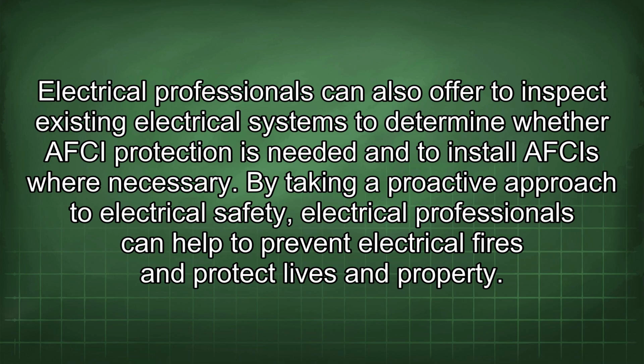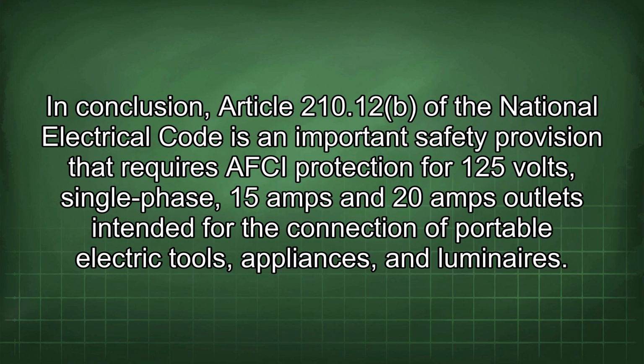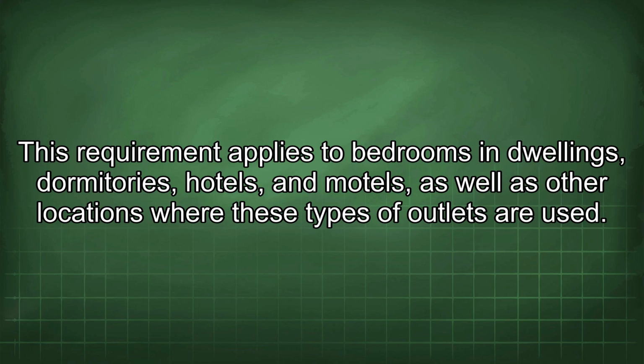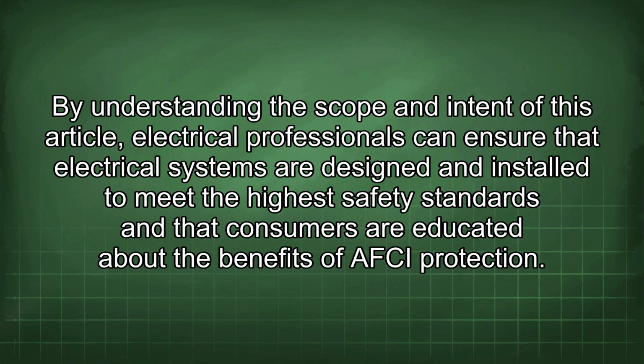In conclusion, Article 210.12 of the National Electrical Code is an important safety provision that requires AFCI protection for 125 volts single-phase, 15 amps and 20 amps outlets intended for the connection of portable electric tools, appliances, and luminaires. This requirement applies to bedrooms in dwellings, dormitories, hotels, and motels, as well as other locations where these types of outlets are used. By understanding the scope and intent of this article, electrical professionals can ensure that electrical systems are designed and installed to meet the highest safety standards and that consumers are educated about the benefits of AFCI protection.